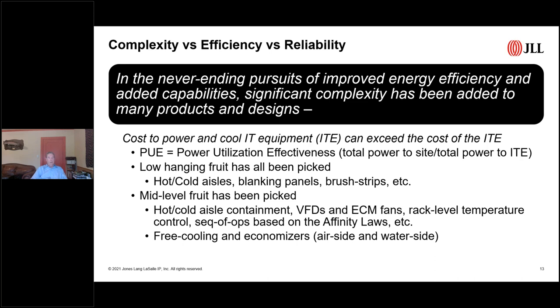Then we went after the mid-level fruit. We started using hot aisle containment, retrofitting equipment with variable frequency drives and ECM, electronically commutated motor fans, etc. We started applying rack level temperature control and all these other things. And now we're using free cooling and economizers almost everywhere, both airside and waterside.